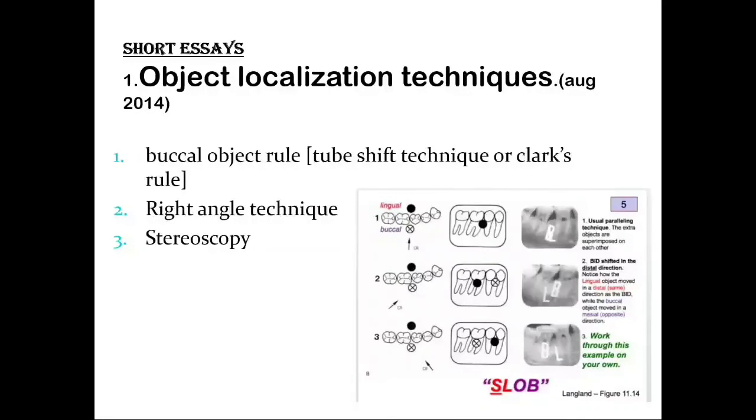Then you have stereoscopy, which helps to determine small intracranial calcifications and foreign bodies in dense or thick sections. Stereoscopic imaging exposes two films, one for each eye, so it delivers twice the amount of radiation to the patient. Between the exposures, the patient is maintained in position, the film is changed, and the tube is shifted from the right eye to the left eye position. After processing, the films are viewed with a stereoscope using either mirrors or prisms, so as to coordinate the accommodation and convergence of the viewer's eyes, so that the brain can fuse the two images together.